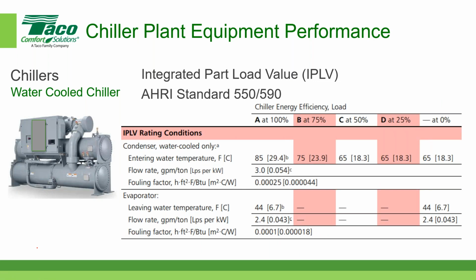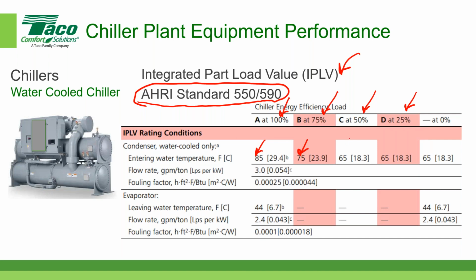Now, the other thing that chiller manufacturers publish is called the Integrated Part Load Value, or IPLV. The IPLV is a standard established by the American Heating and Refrigeration Institute, Standard 550-590. What it's telling us is that chillers don't operate at peak energy consumption all the time. They look at the chiller performance for 100% load, 75% load, 50% load, and 25% load. Especially for water-cooled chillers, they take those readings at different condenser water temperatures. 85 is the maximum, then 75, where they take credit for it, then 65, and then it levels off at 65 down here.